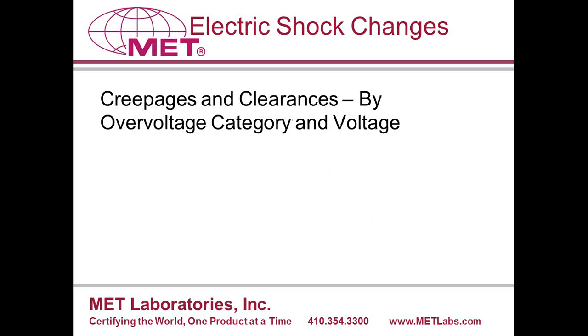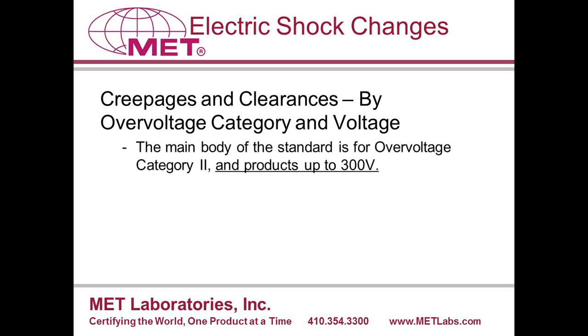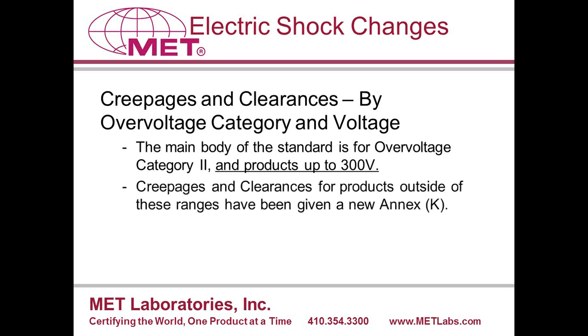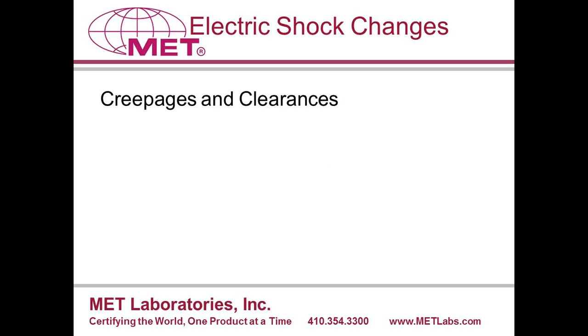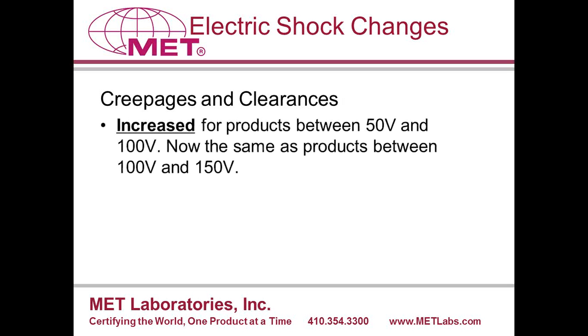Since the majority of products fall under overvoltage Category 2, and under 300 volts, these are the focus of the body of the 61010-1 standard. However, for products between 300 and 1,000 volts, or used in Category 3 or 4 installations, the third edition standard has a new Annex K, which gives creepages and clearance and dielectric strength values for those cases. Similarly, the limits for products covered in the standard have gone from 600 to 1,000 volts. This doesn't affect most North American or European products.